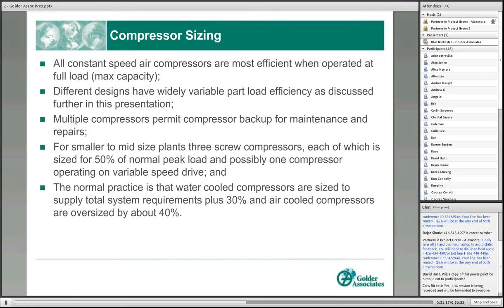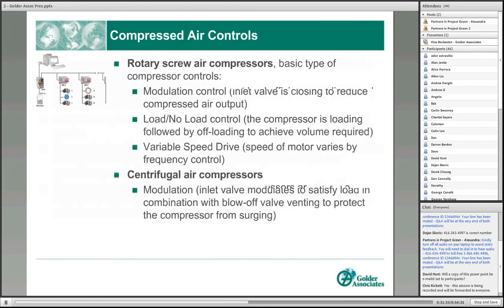On larger systems, the rule of thumb tends to be, on water-cooled systems, 30% over design in the size of the compressor capacity, so that you can handle some extreme peaks or some maintenance shutdown of one of the compressors.